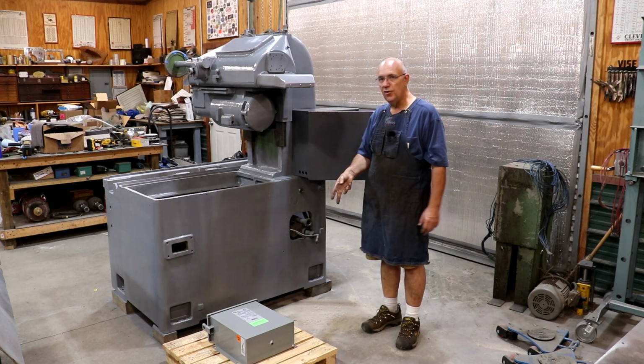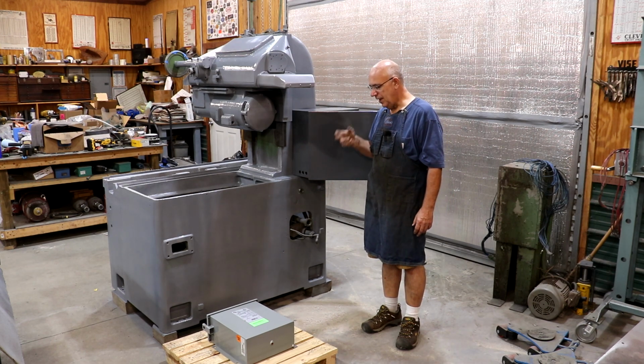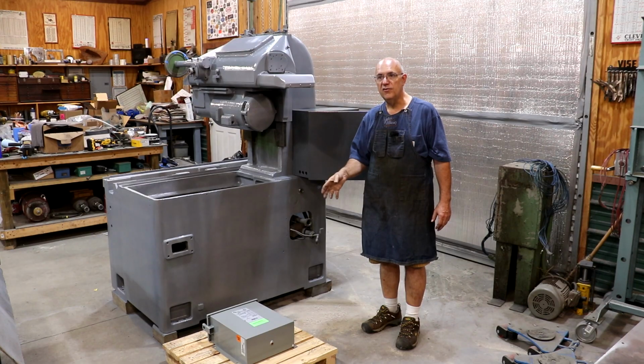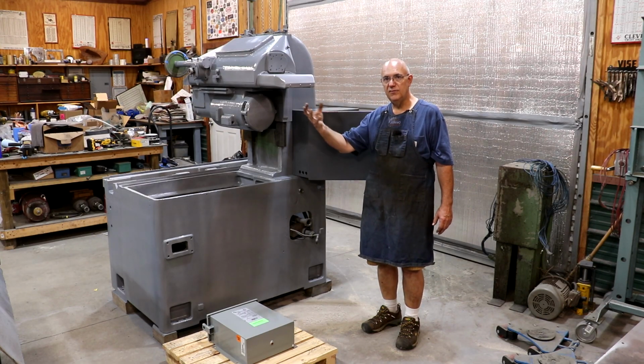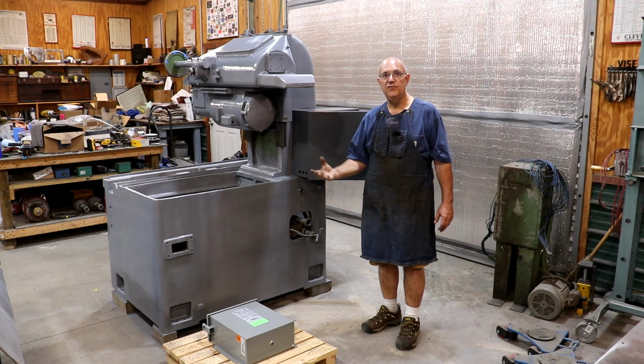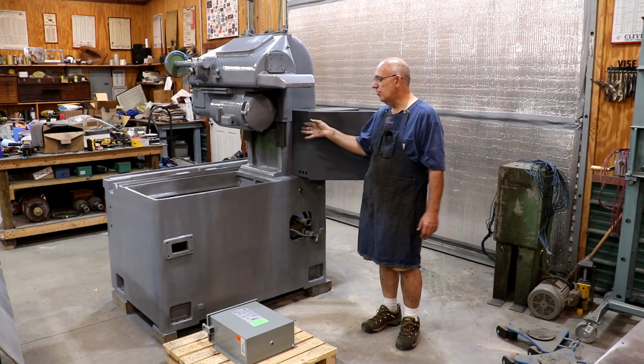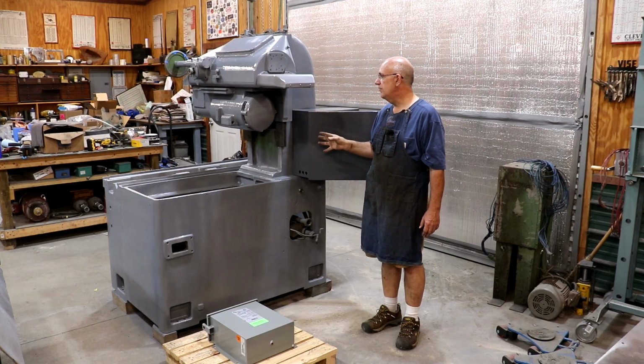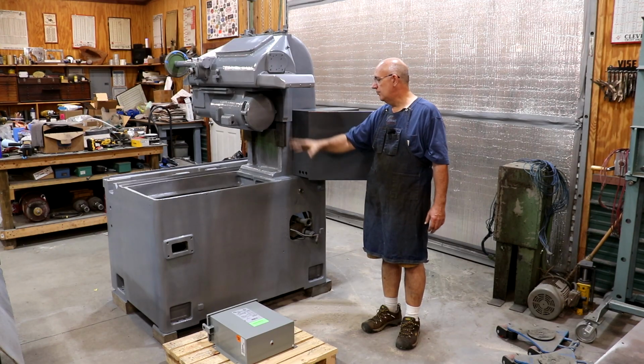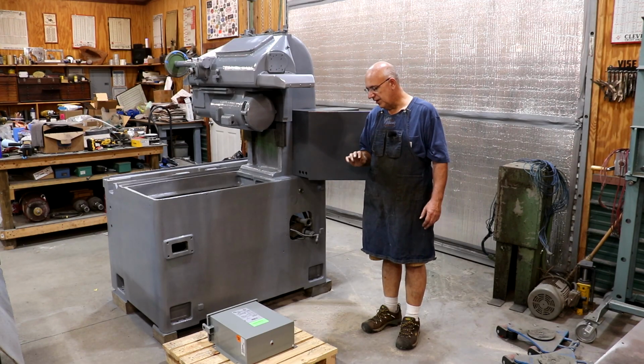We'll give it 220 volts at 30 amps, and that will change it over to 440 volts. Since we're doubling the voltage, the amperage will go in half, down to 15 amps. But at 440 volts, 15 amps is more than enough - I did the math to run all these motors. So that's what we got.